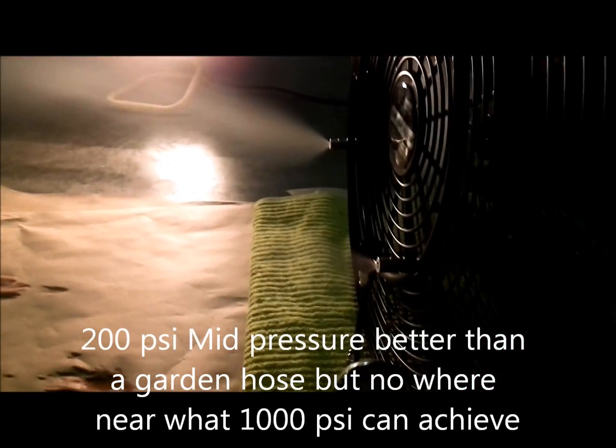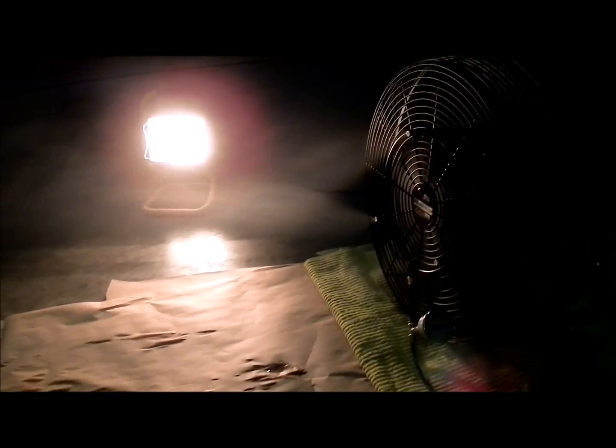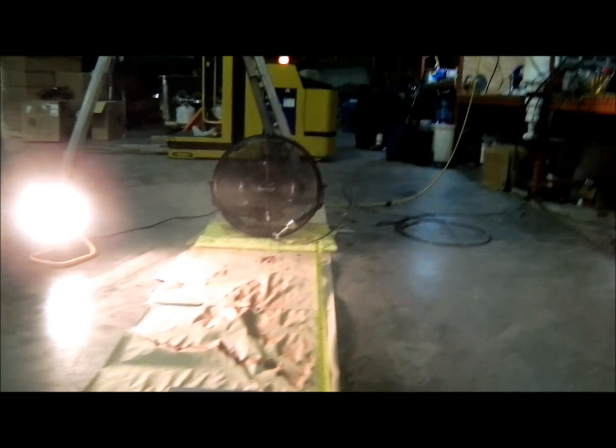Now we're showing the 200 psi system. You can see we're getting some water buildup on the paper — we just started running this about 30 seconds ago. Same conditions as the 1000 psi system, and already we have lots of water accumulating.